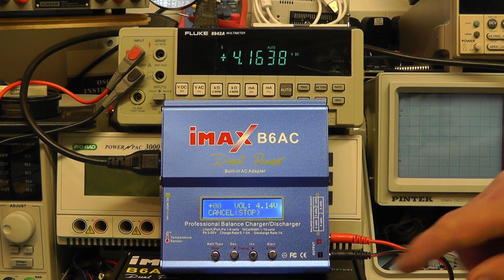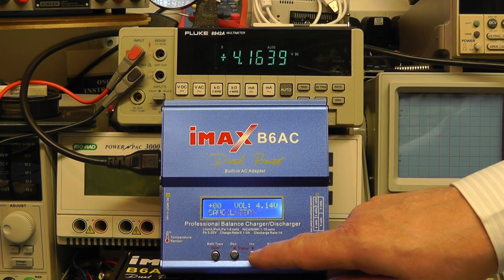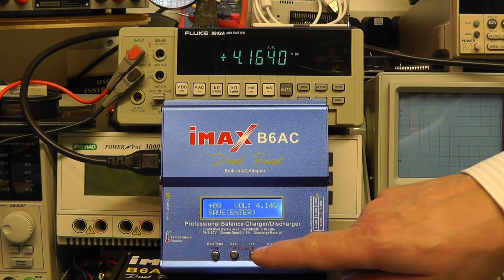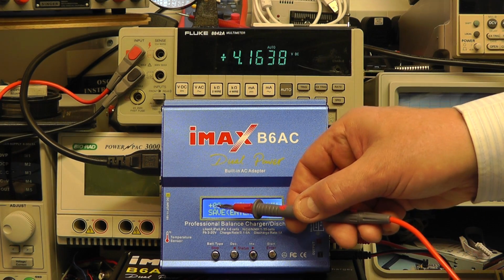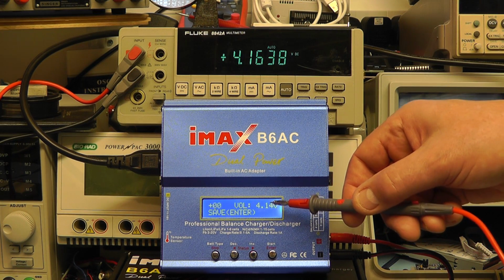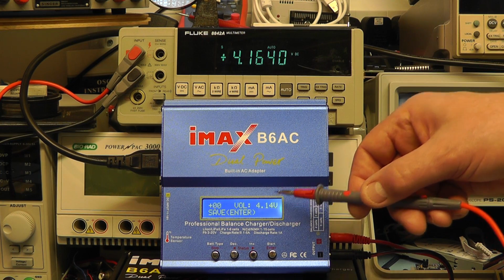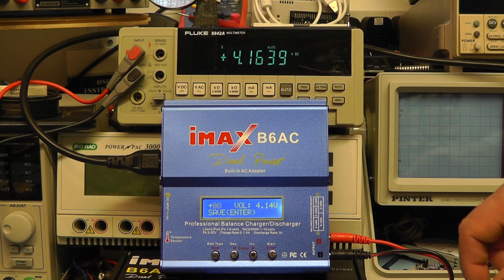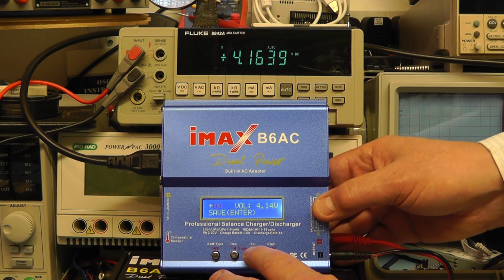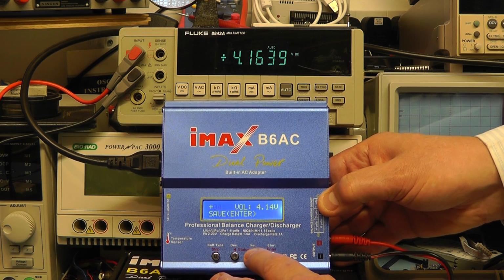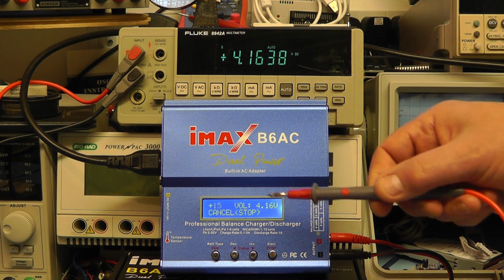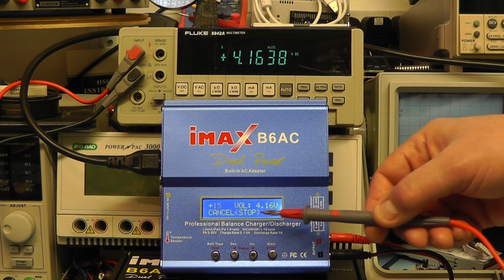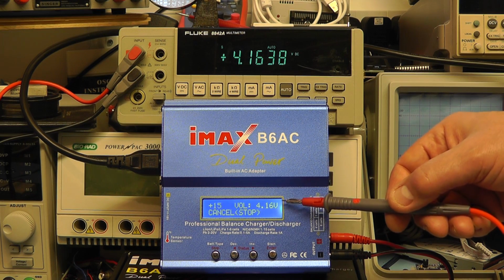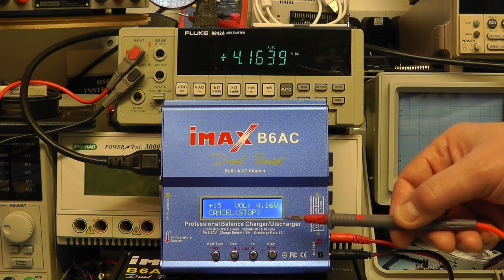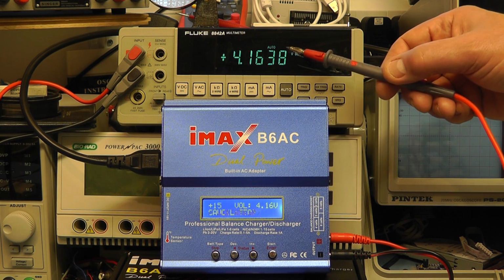To do that it's quite simple. You use either the decrement or the increment button. Well, obviously we want to increment now, so as I press the increment button, you'll see the reading start to go up, and eventually we should get to a point where the 4.14 volts reaches the correct voltage for this battery of 4.16. So I'll do that now. There we go. You see I've put an adjustment in there of plus 15, and that has now corrected the voltage reading on the charger to read exactly 4.16, which is the same as the multimeter is displaying.